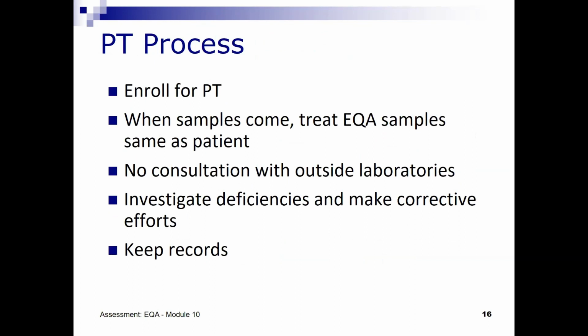Okay, so here are the 5 steps for a proficiency testing process. The first step is to enroll in some proficiency testing schemes. There are many local ones throughout sub-Saharan Africa, but there's also UK NEQAS, which is quite popular. There are all the ones that the College of American Pathologists deploy. And then there are many other groups. There are some EQA schemes that are local. I know that Pathologists Overseas supports some EQA proficiency testing labs with materials from the Royal College of Pathologists of Australia. So the first step is to enroll.